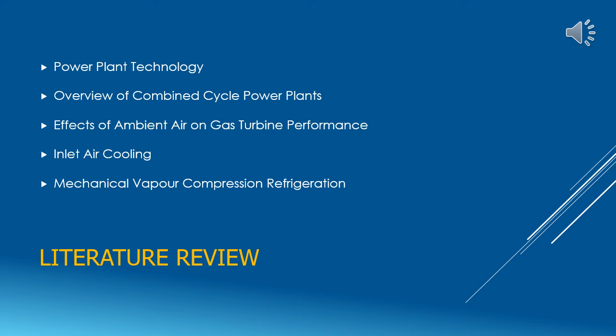Primarily, research papers, articles, and textbooks were used for literature in this study thus far. They aided in the overview of the combined cycle power plants and its different components and how they each play a role in generating power output to the country. Studies have shown the negative effects that ambient air temperature has on the gas turbine performance. It can be said that the gas turbine's output is inversely proportional to the ambient temperature. Additionally, research has also shown how inlet air cooling can help with the effect of the ambient temperature on the gas turbine by reducing its temperature from an average of 27 degrees Celsius to the required ISO condition of 15 degrees Celsius to obtain its desired performance. And lastly, an understanding of the mechanical vapor compression refrigeration system and how it can be adapted to the workings of the gas turbine on a combined cycle plant was gained.